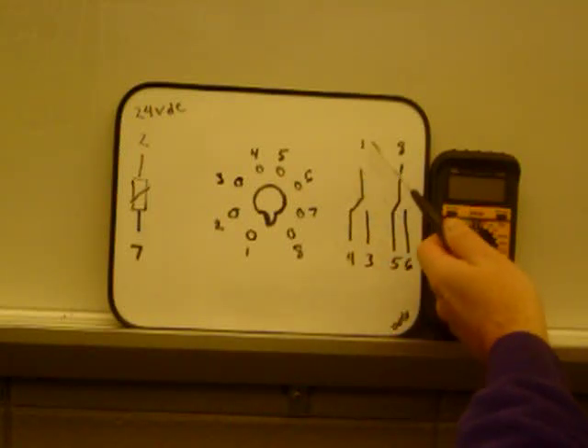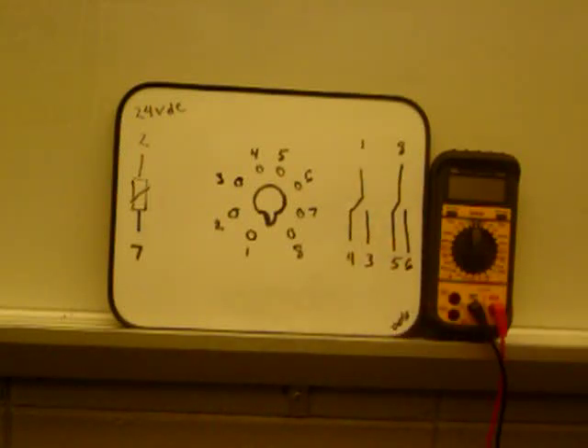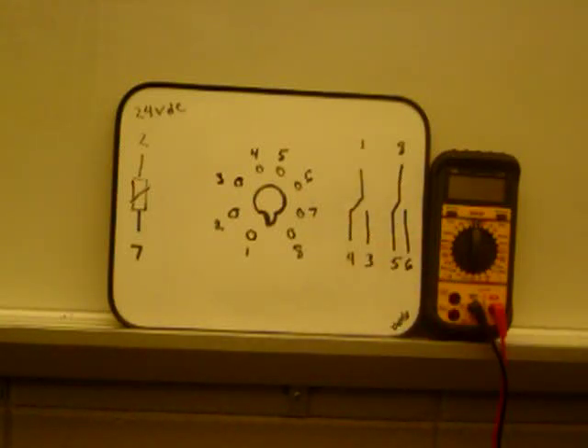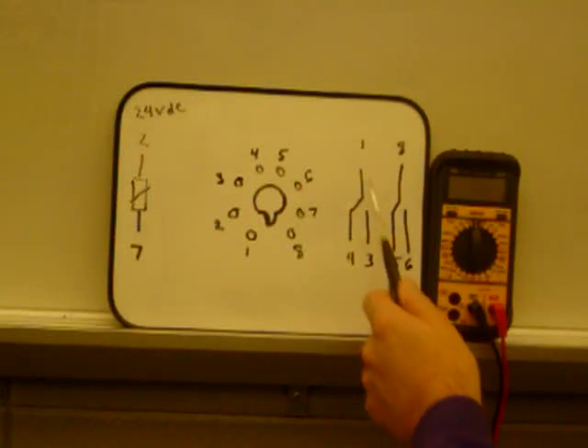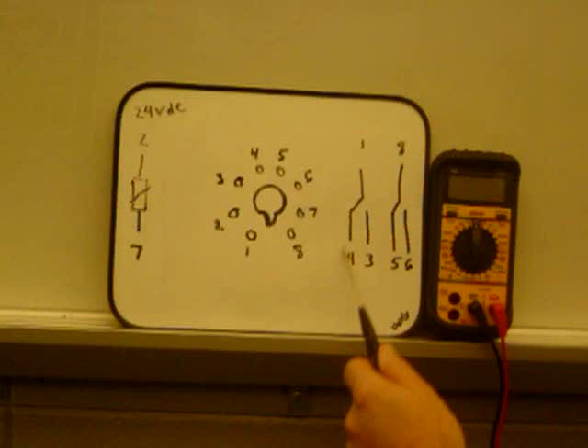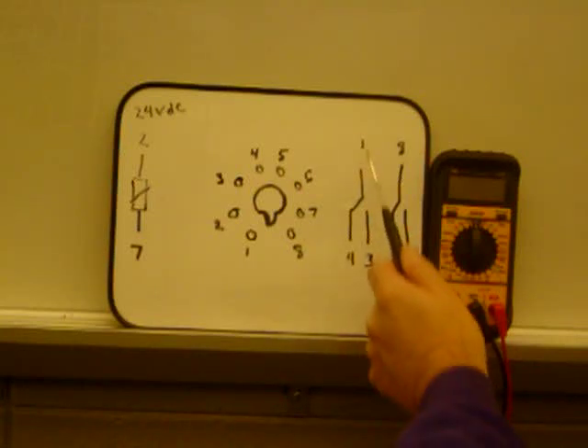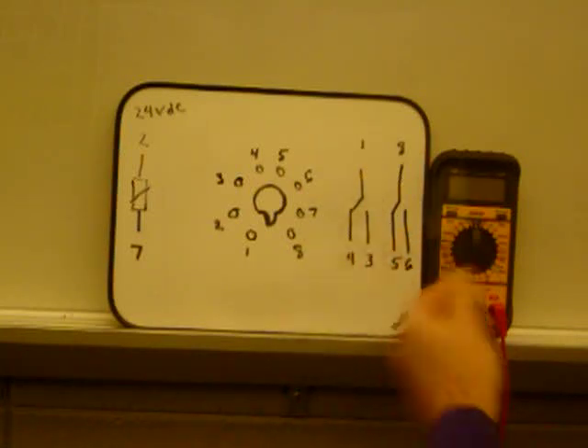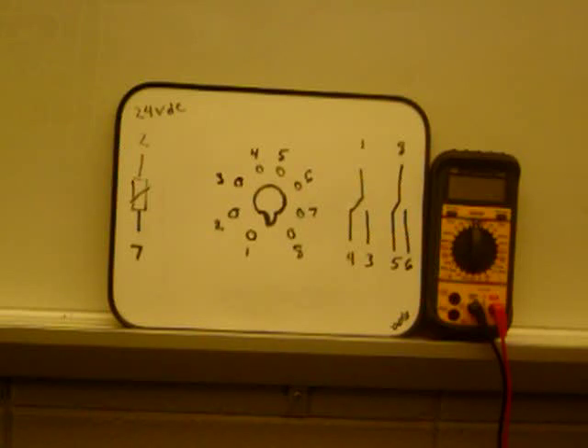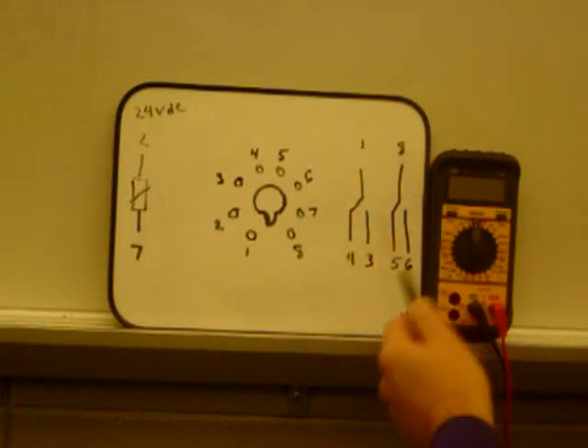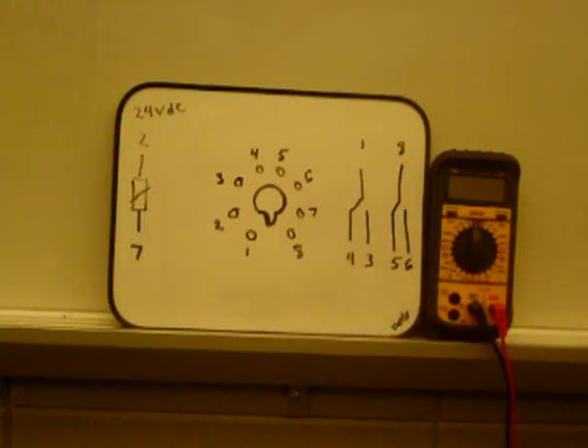That means that one to four is a normally closed set of contacts, whereas one to three is a normally open set of contacts. A lot of these relays will do that where you can choose either to use normally closed one to four so that when it energizes, this opens, or you can choose normally open one to three so when it energizes, it closes. So they give you a lot of versatility with these things, and of course it's symmetrical. I've got eight, five, and six works the same as one, four, and three.